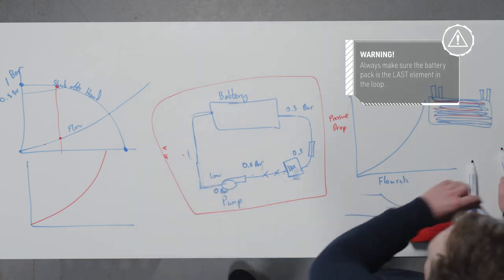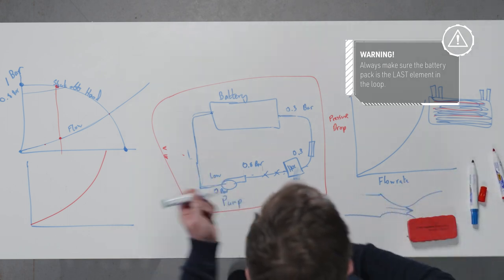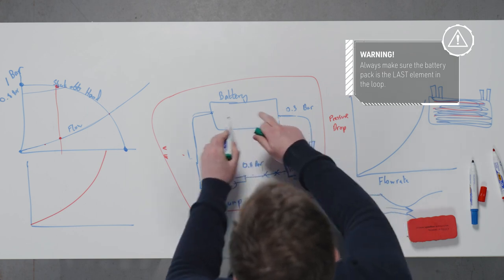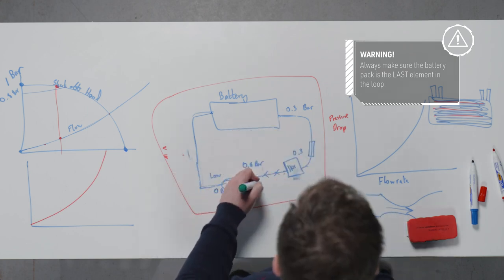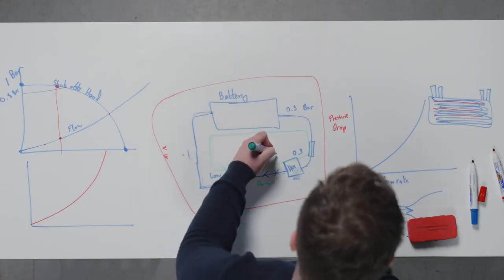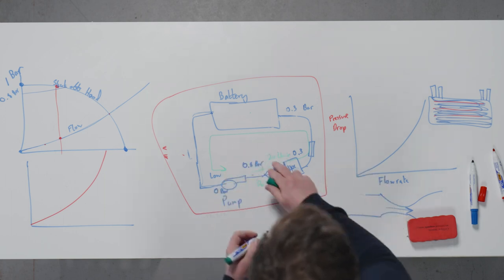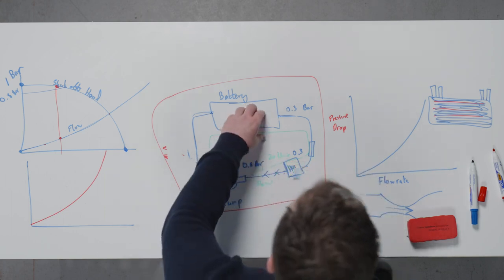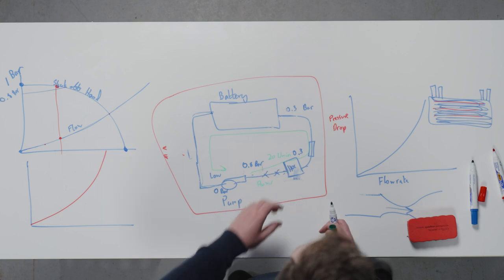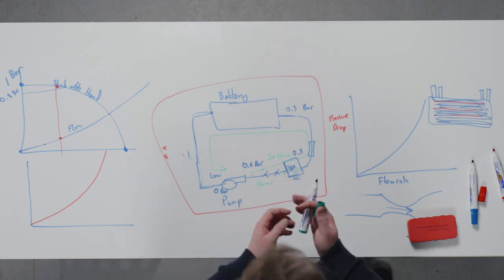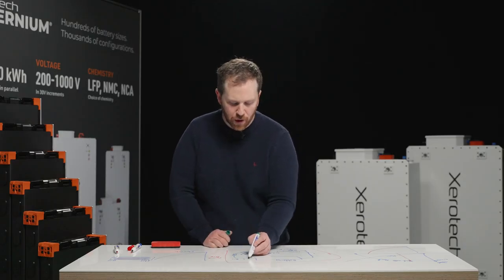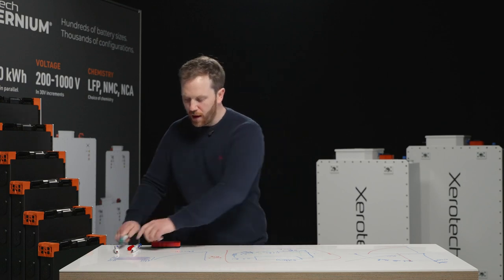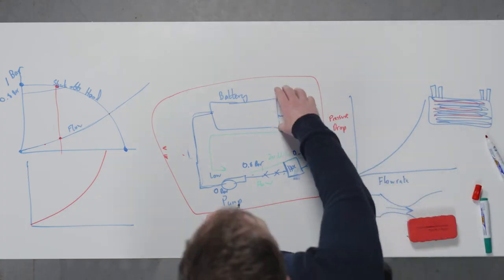In the loop that we've drawn here, it doesn't matter where you put any component in the loop. The flow will be constant through this loop. It's always the same flow. It could be 20 liters a minute through this loop. But by moving the components to different points, they can experience very different pressures. So this battery pack here is only experiencing a pressure of 0.3 bar on its inlet side.